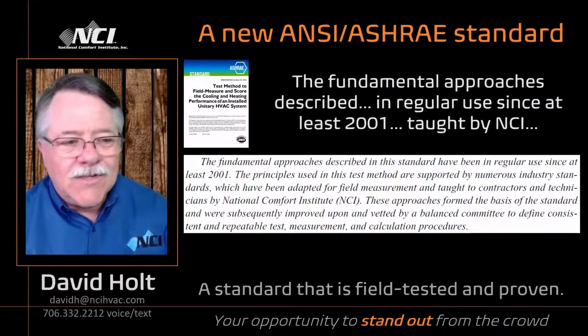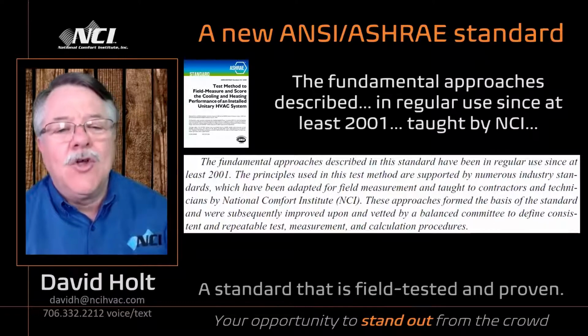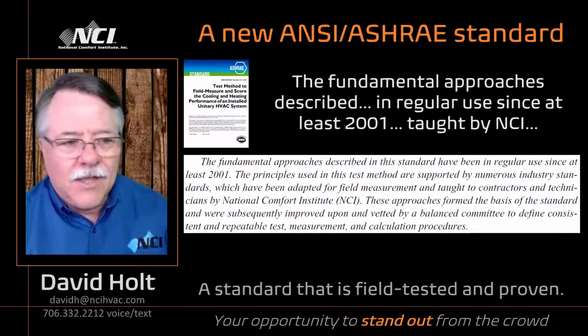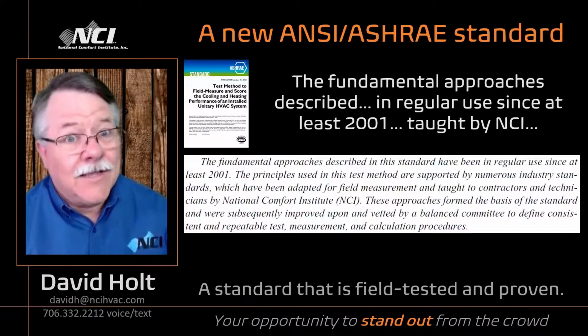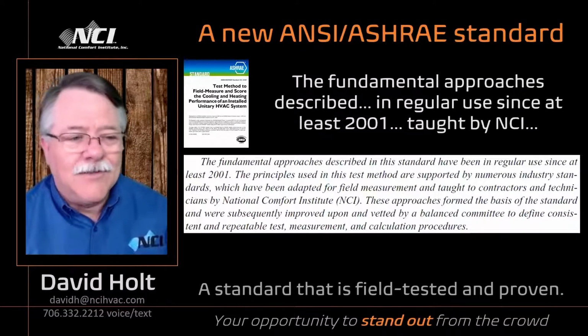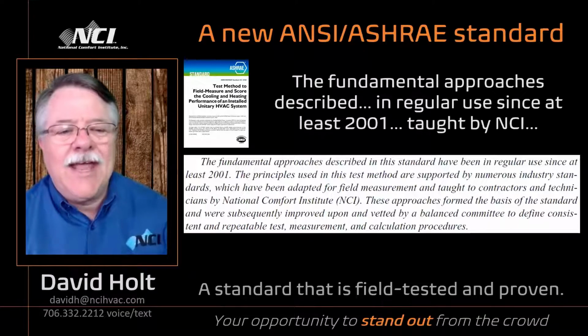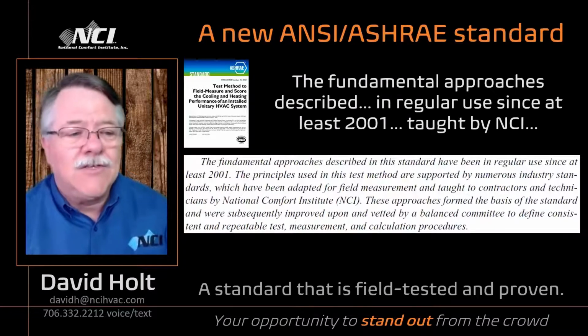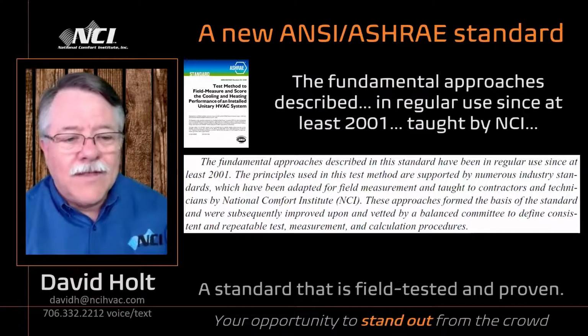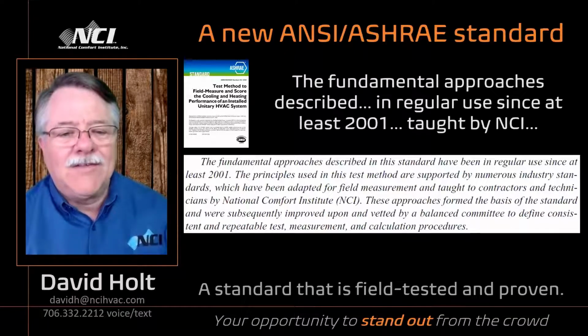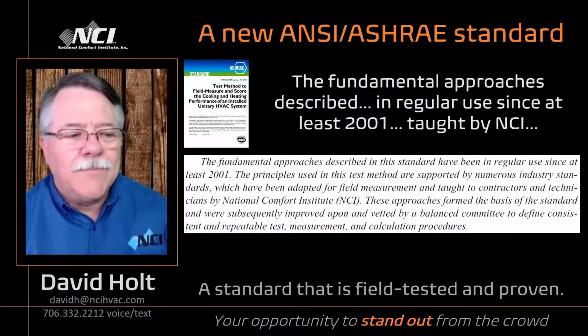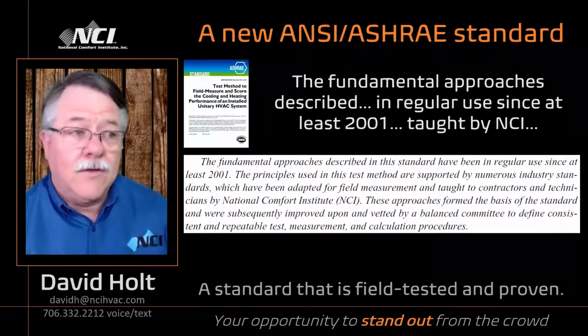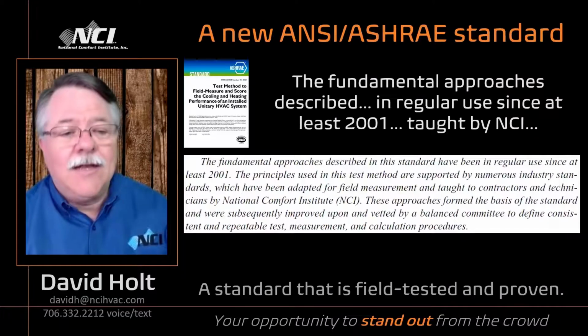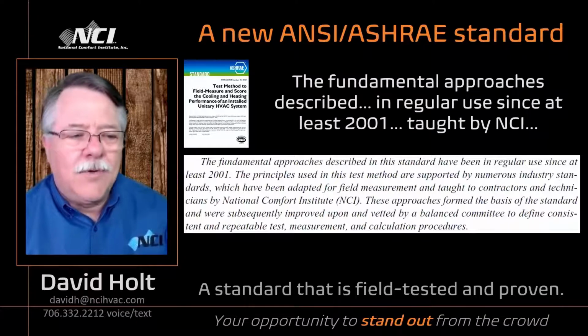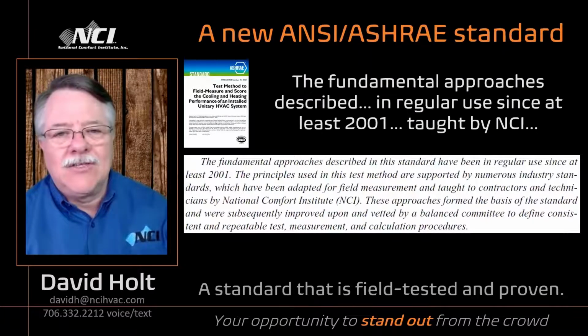So this fundamental approach described in this standard has been in regular use since at least 2001. The principles used in this test method are supported by numerous industry standards, things like ACCA and NCI, which have been adapted for field measurement and taught to contractors and technicians by National Comfort Institute. These approaches formed the basis of the standard and were subsequently improved upon by ASHRAE and ANSI, and vetted by a balanced committee to define consistent and repeatable test, measurement, and calculation procedures.